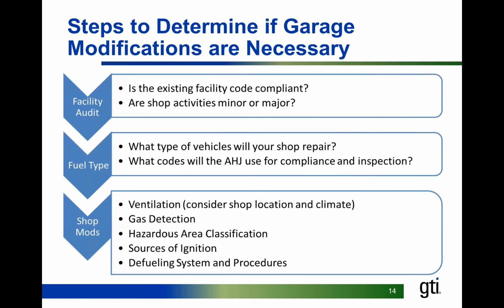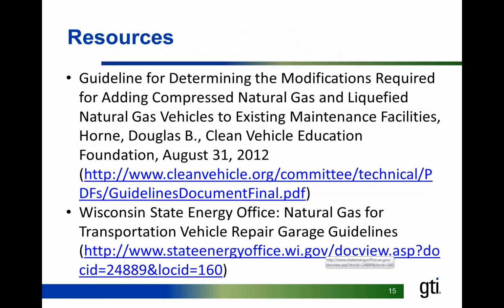So when you look at the major steps to determine if or how extensive modifications are needed, the first thing is your facility audit. You'll look to see if you're code compliant to begin with for traditional fuels. You look to see if you have minor or major repair activities. The second step is to look at your fuel types, the types of vehicles that you're planning to do maintenance on. That will drive you to your codes, as well as your local authority having jurisdiction, your local code official. Then look at the shop modifications: ventilation, gas detection, hazard area classification, sources of ignition, and procedures. There are some more examples and really good resources online, that are free, that can help you go through this and see.